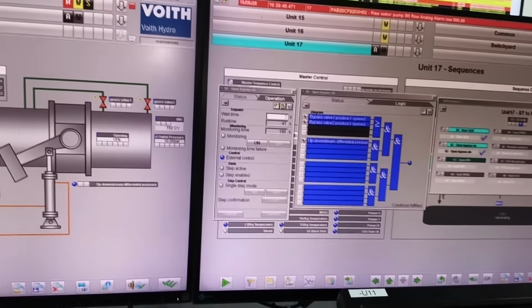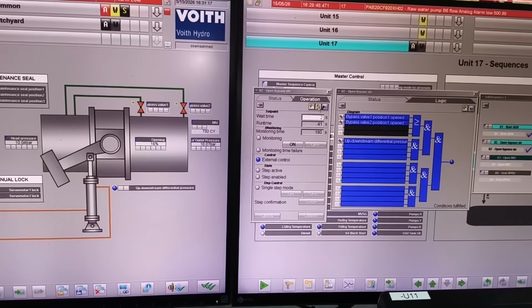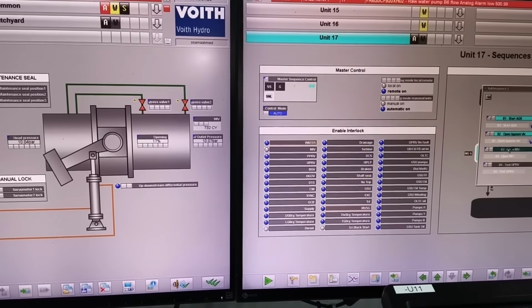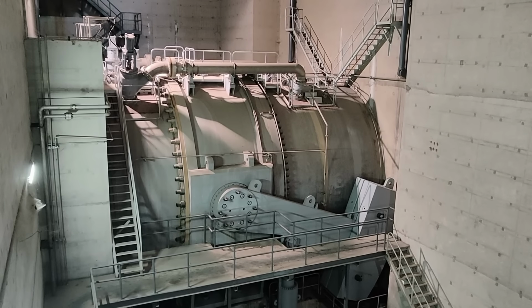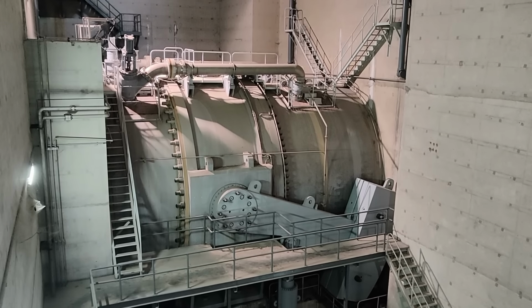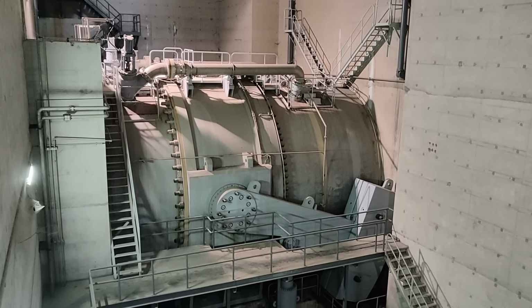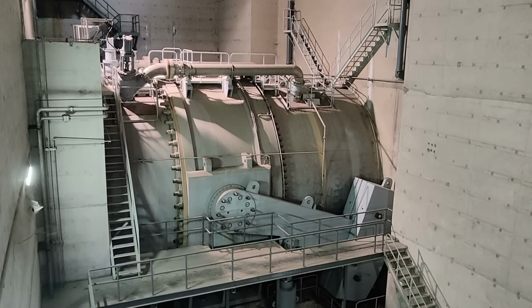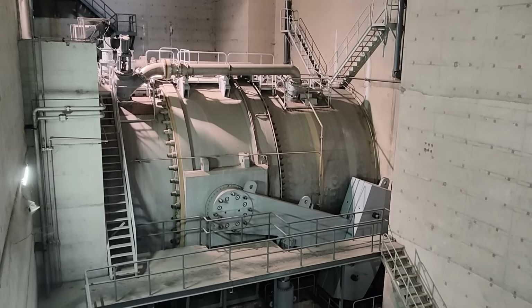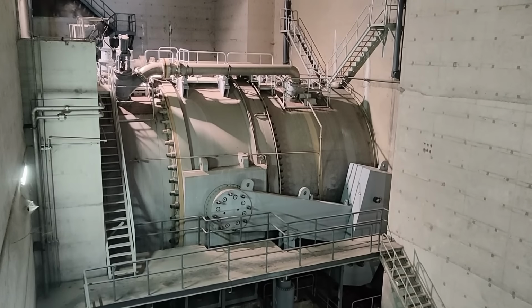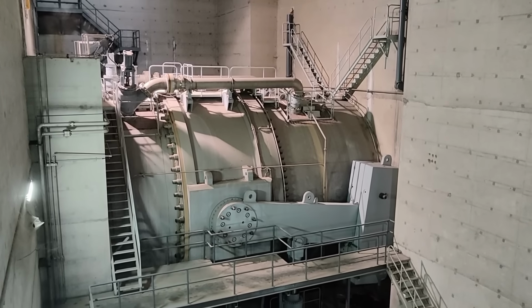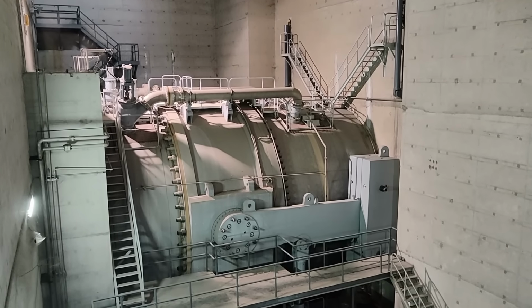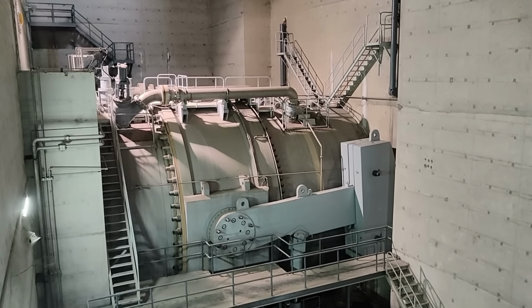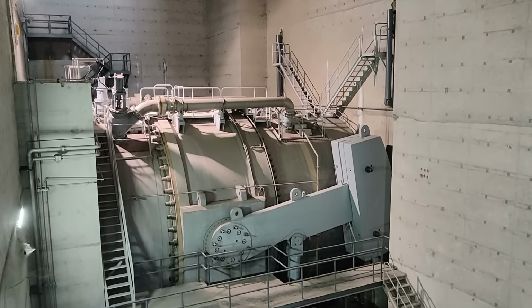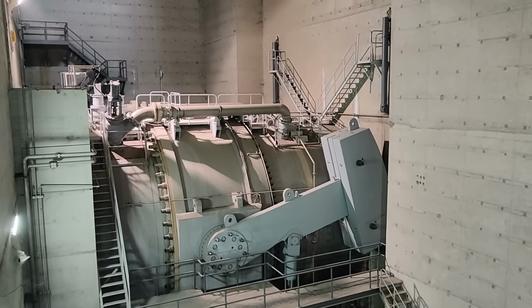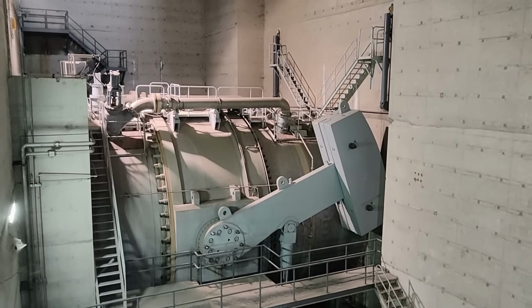Now that pressure is balanced on both sides, the main inlet valve or MIV can safely begin its opening. And yes, many of you asked about the size of this penstock in the previous video. The diameter of this penstock is about 10 meters. I will speed up this section a little so that you can see the important movement. Watch carefully. The MIV gradually moves towards a fully open position, and notice something interesting. As soon as the main inlet valve is fully open, the bypass valves close again automatically because their job is finished.